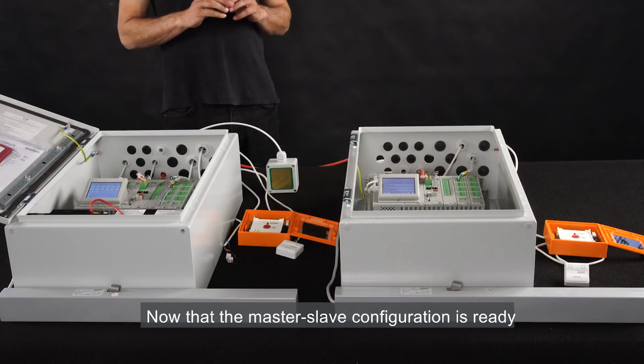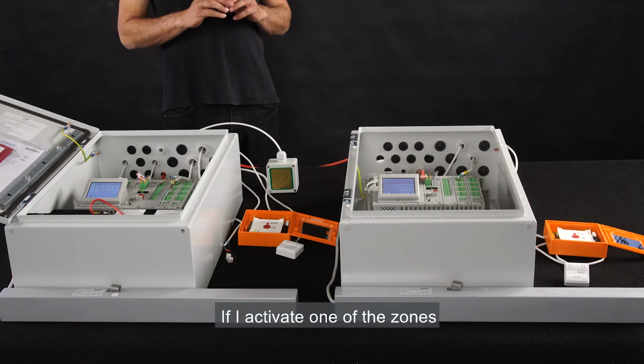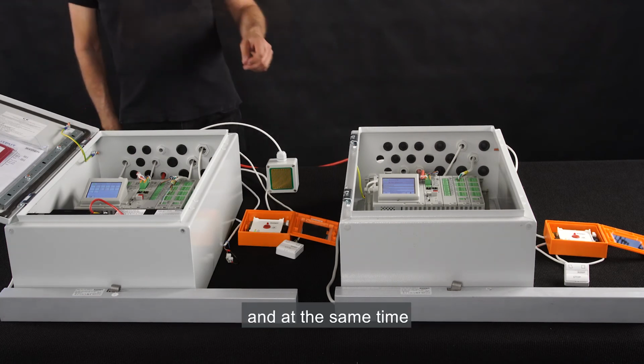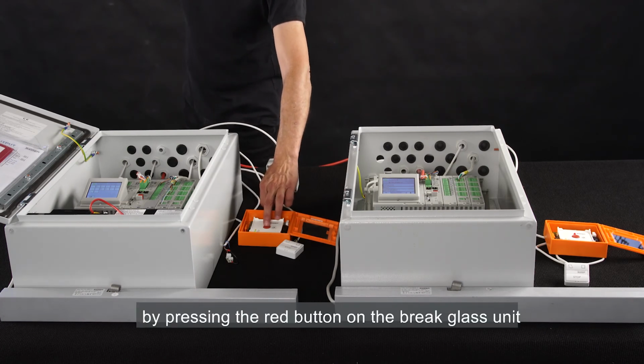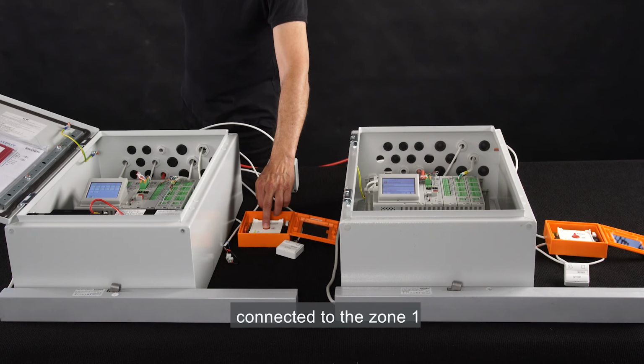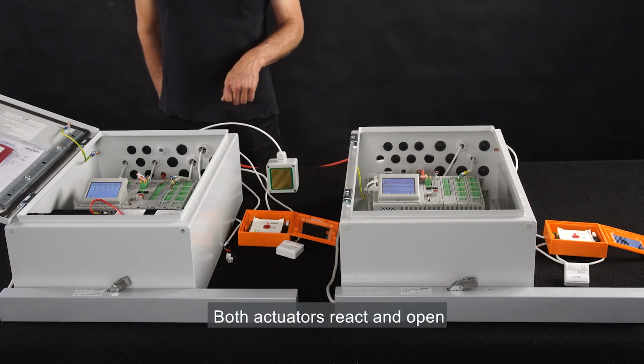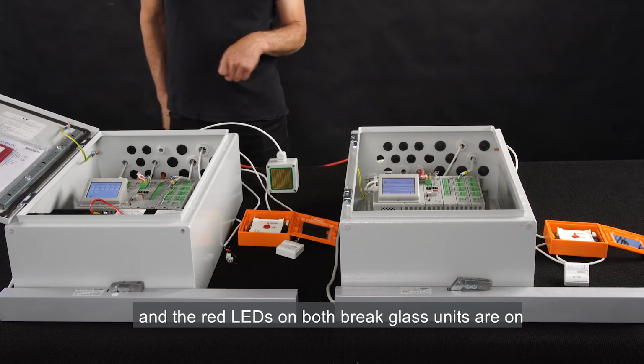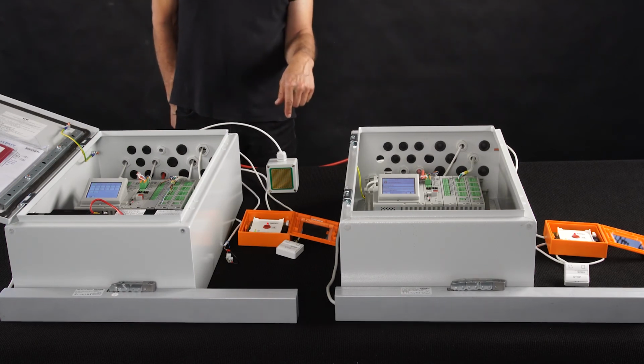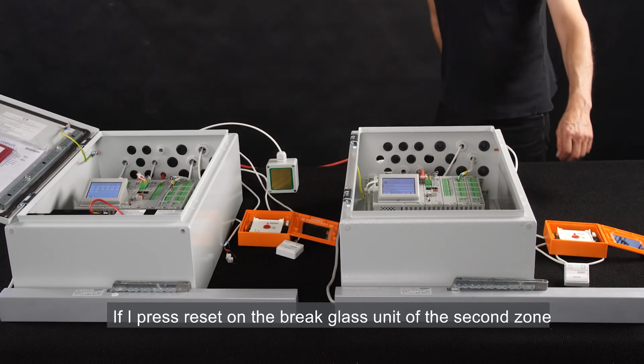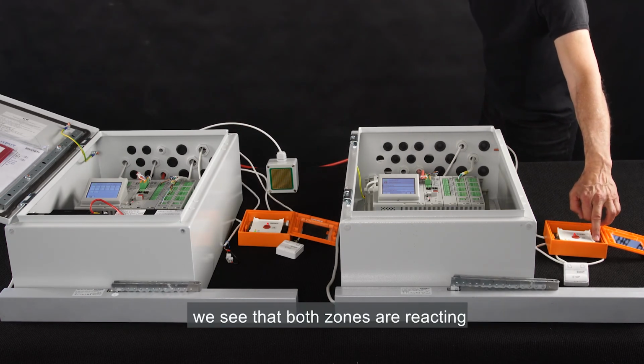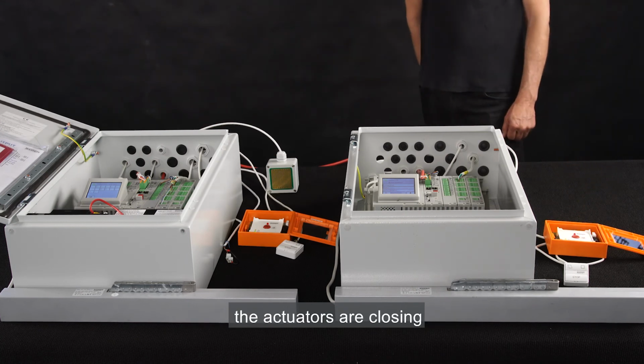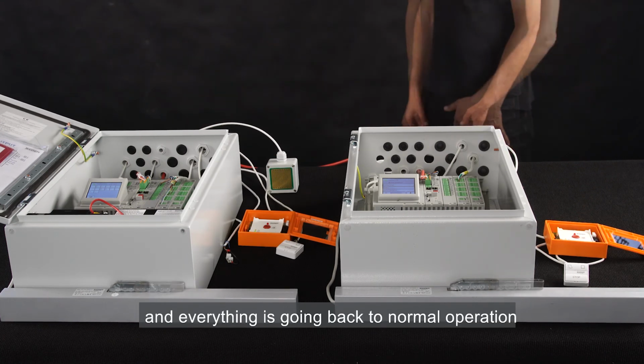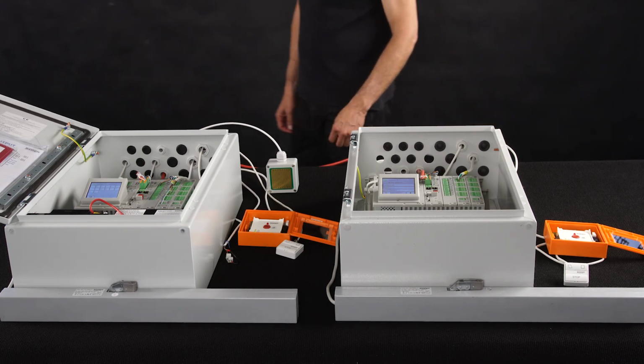Now that the master-slave configuration is ready, let's check that everything is working accordingly. If I activate one of the zones, the other one will react in the same way and at the same time. I activate the fire alarm by pressing the red button on the break glass unit connected to Zone 1. Both actuators react and open, and the red LEDs on both brake glass units are on. If I press Reset on the break glass unit of the second zone, we see that both zones are reacting, the actuators are closing, and everything is going back to normal operation.